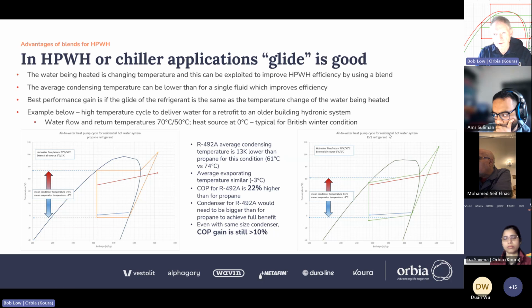So the worst case for a Lorenz cycle is a single fluid where you're at a pinch at one end of the heat exchanger. So on the left I've shown an air-to-water cycle for propane, and you can see for the conditions I picked, which is actually fairly typical for a heat pump in winter, where you're trying to make domestic hot water for an old-fashioned radiator system, then you might have the actual mean evaporator temperature being -3C and the condenser temperature being +74C to give you a hot water flow return 70C, 50C.